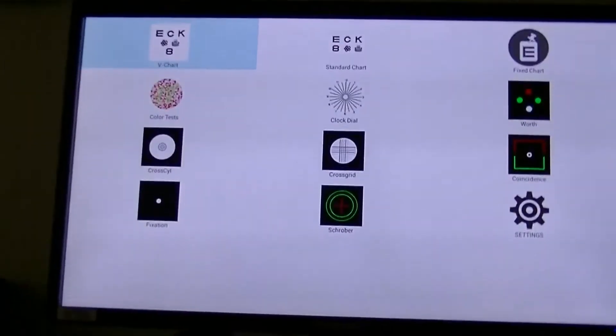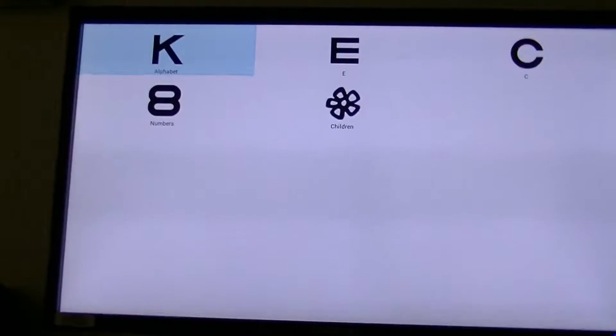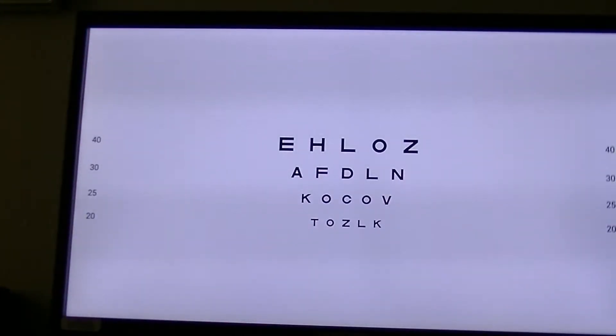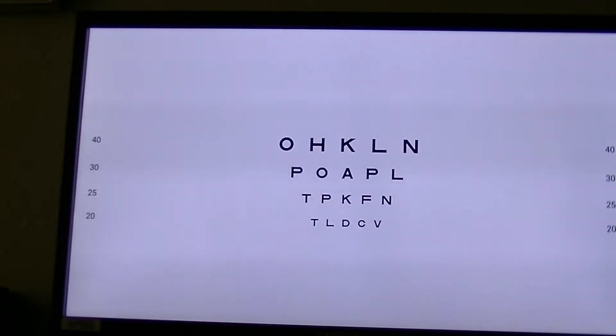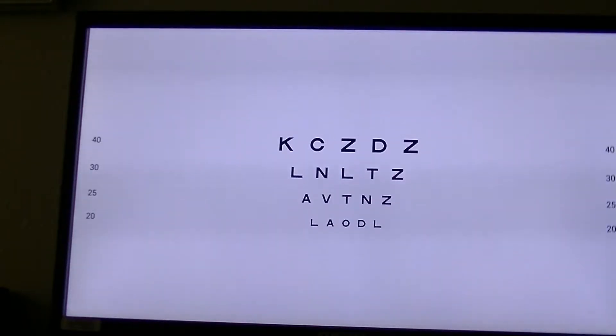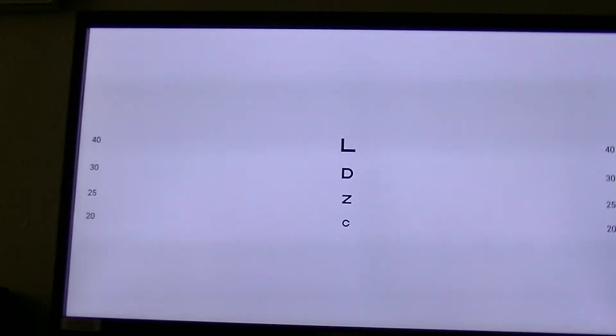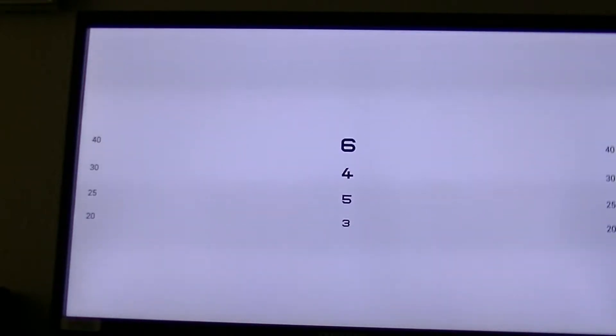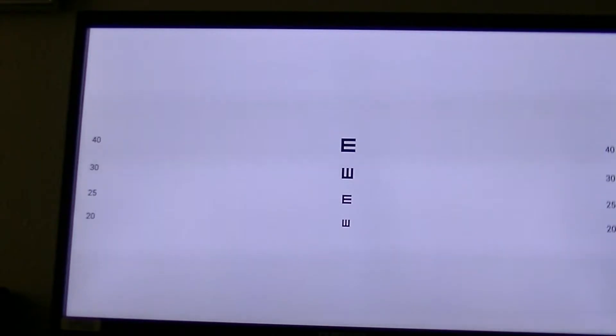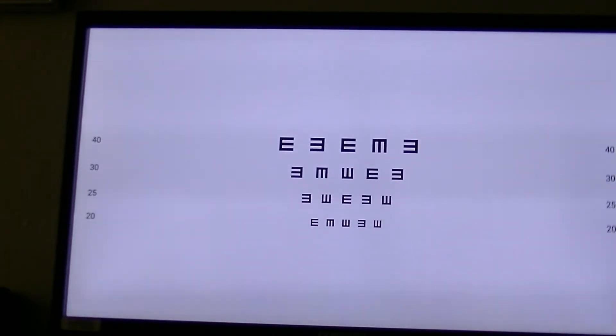Now you're back in. When we come back to this chart, it won't be mirrored and the units will be smaller. Alphabet — and boom. Now you're not mirrored and you're smaller. Remember what I said about randomizing? That's the right arrow on the right-hand side — that will randomize every chart, every time. And again: single letter, single line, or vertical line. Want to randomize it? Hit randomize. Want to change it to numbers? Just hit the numbers. Want to change it back to E-game? Hit that. Want to go back to the regular Snellen chart? Go back using that left rewind button, which takes you back to the previous screen.